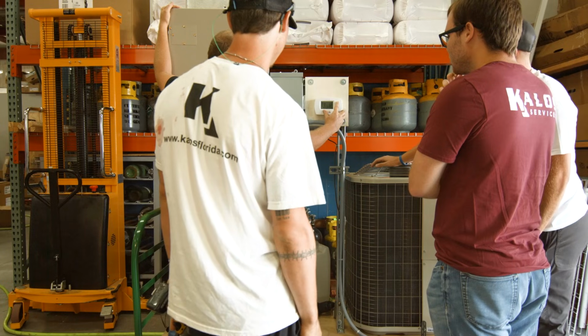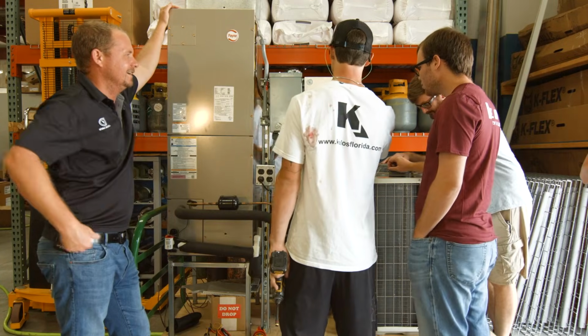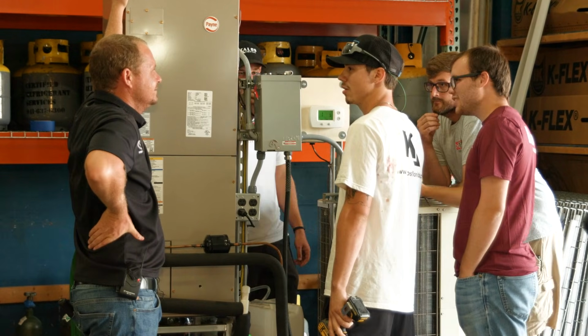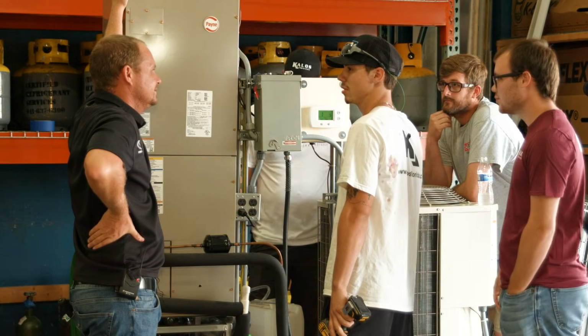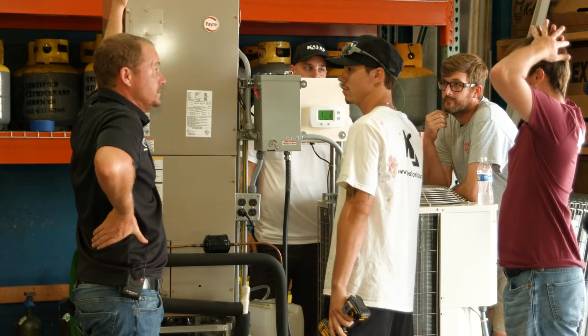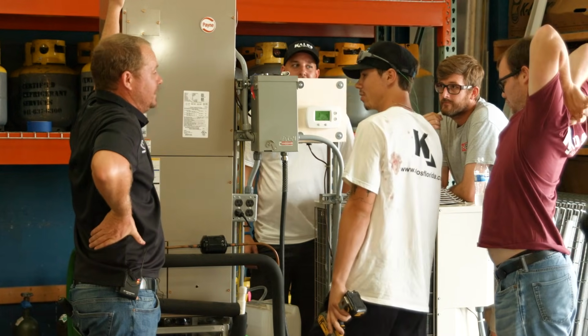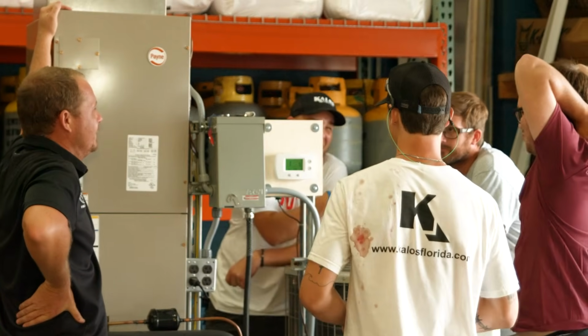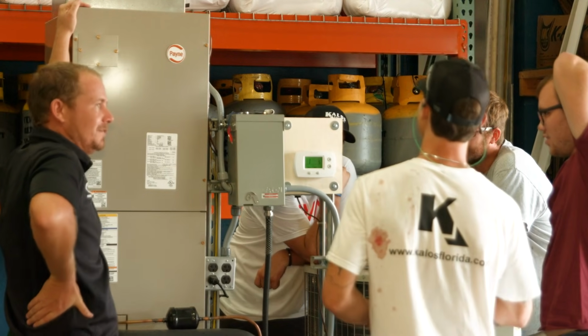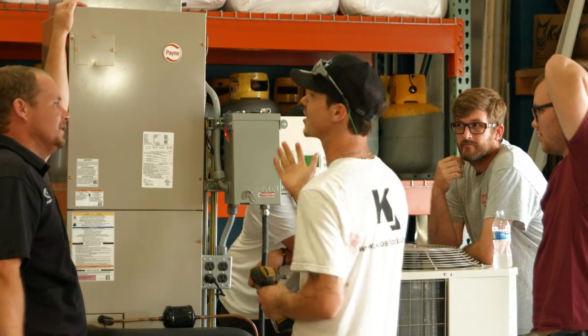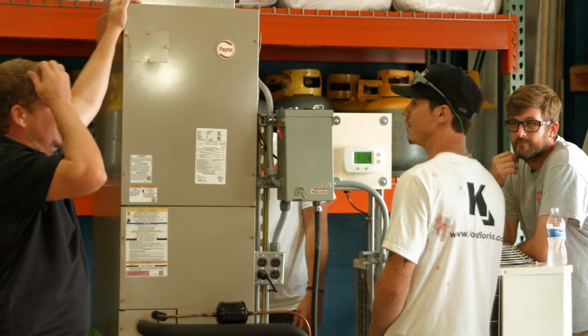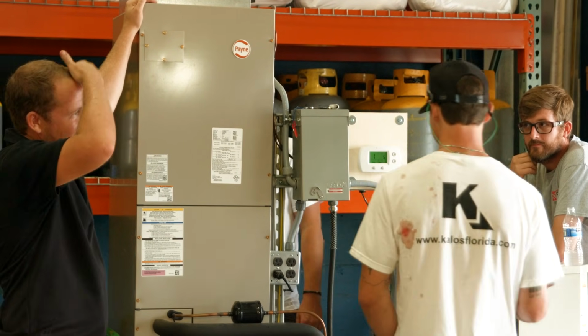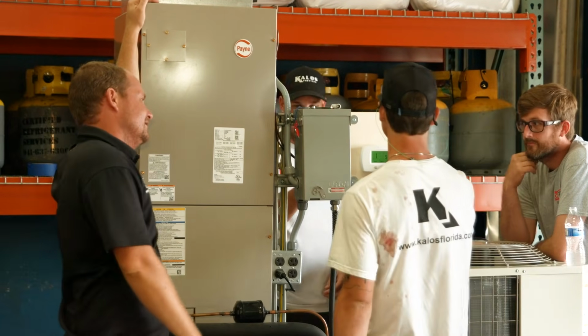So I had set this to straight cool, it should be cooling, it shouldn't be... I know, why is it? It should have been in heat mode. So thermostat wasn't. So why isn't it in heat mode? That's interesting, now we're finding a different problem than we originally even thought we were finding. That was the problem I put into it, it was supposed to be programmed incorrectly, and I was going to test you to see if you could catch that, because you've never made that mistake before.